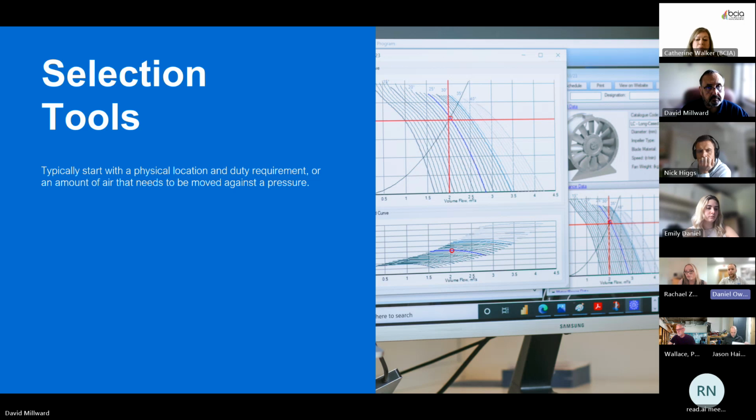And then as Dave touched on earlier, we're getting a lot of buildings that were built for a particular use, but then things change and the standards that you have to meet also change. So we could be looking at applications where we're retrofitting products, replacing old technology, old fans or reworking air handling units. And so this stipulation could be around getting a replacement unit into a space, which could be problematic or challenging. Or on the flip side, if it's a new build, the space may not be so much of an issue, but you need to consider future maintainability needs, and for things such as filter replacement or the servicing of motors for bearings or troubleshooting issues with smart controls.